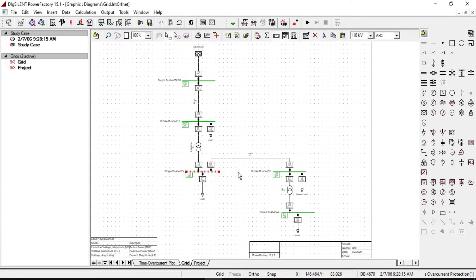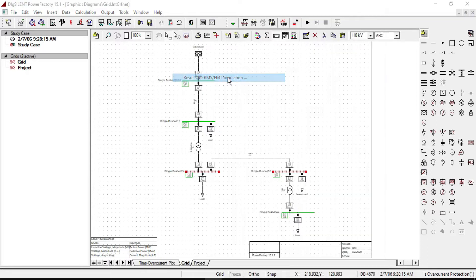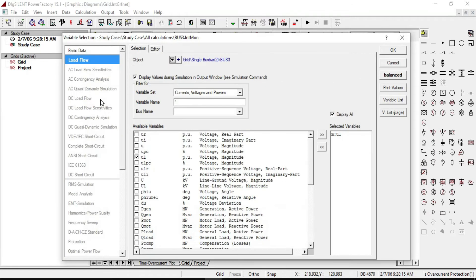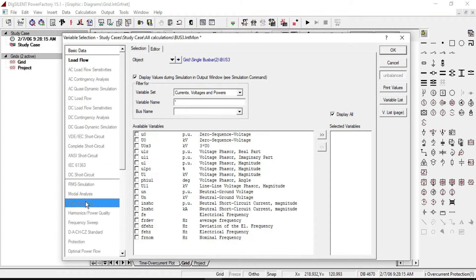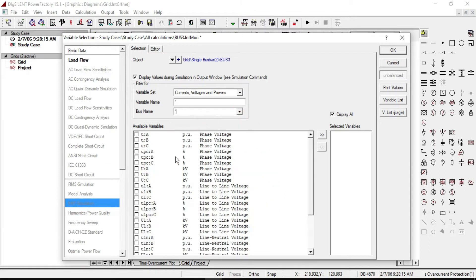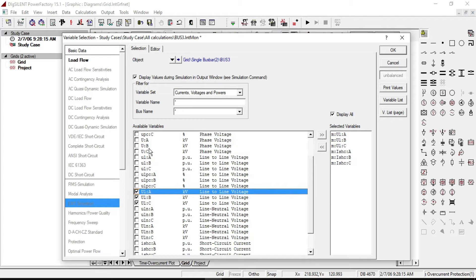First, select the bus bars, right click, and from Define click Results for RMS/EMT simulation. Then double click on bus 3 and in the variable set select current, voltages, and powers, then select all bus bars using EMT simulation. Select line-to-line magnitude voltage of phase A, phase B, and phase C, also the magnitude of short circuit currents for phase A, phase B, and phase C. You can also select per unit values of the three phase voltages and short circuit current.